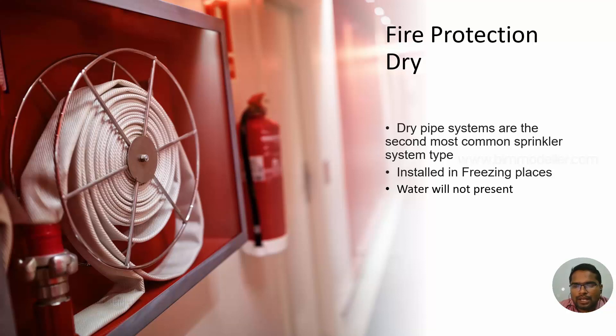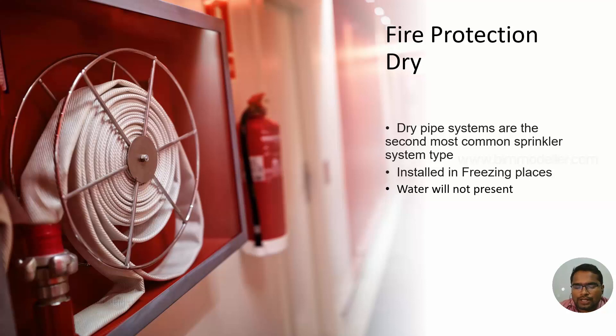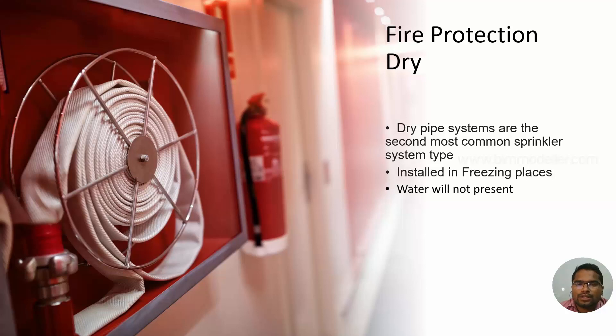Fire protection dry — the name itself tells you the meaning. The pipe will not have water inside. Once the sprinkler blasts, there is a pressure difference in the system and water will pass through later, or pressurized air will be released. Why do we use a dry system? If you are in freezing places — countries or locations near freezing conditions — the water will freeze and you will not have flow inside the pipe. So you need to have a dry system in this case, where water is not present at all times. This is the second most used system in buildings.